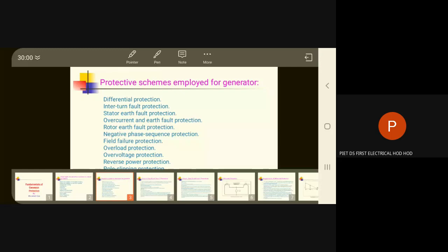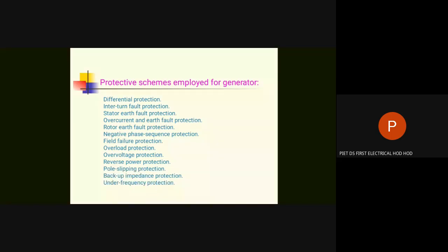what are the protective schemes employed for generators? Differential protection of generator, inter-turn fault protection, stator earth fault protection, overcurrent and earth fault protection, rotor earth fault protection, negative phase sequence protection, field failure protection, overload protection, overvoltage protection, reverse power protection, pole slipping, backup impedance, and underfrequency. These many protections will take not less than 8 hours to cover. Therefore, it will be difficult to cover all these protections in an hour. We'll try to cover as many protections as possible, if possible 3 out of these, in today's talk.